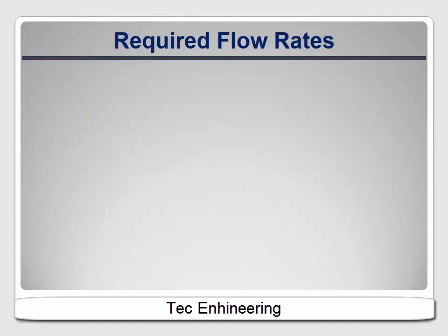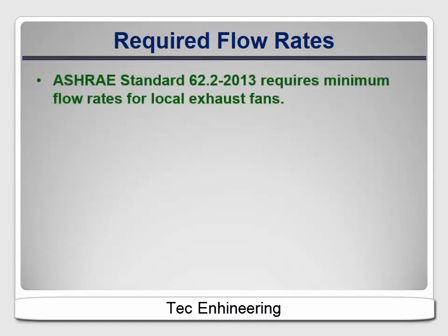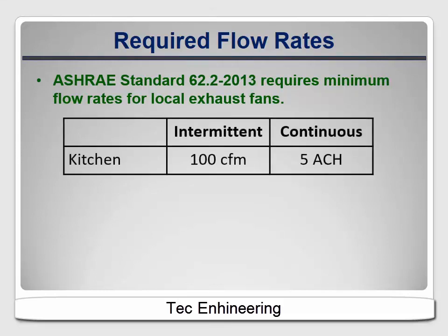ASHRAE Standard 62.2 2013 includes required minimum flow rates for different fan types. The required rates are higher for intermittent systems than for systems that run continuously. For kitchens, intermittent systems like range hoods must provide at least 100 cubic feet per minute of exhaust. Continuous systems must provide at least five air changes per hour in the kitchen, so the bigger the kitchen, the higher the flow rate must be. This has changed a bit in the 2016 version to account for recent trends towards kitchens that are open to the rest of the house; if you're working under that standard, you may need to do some additional research.